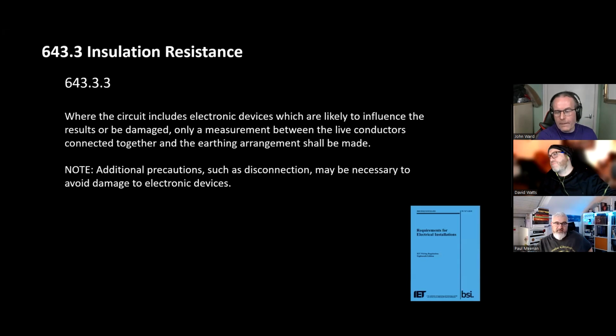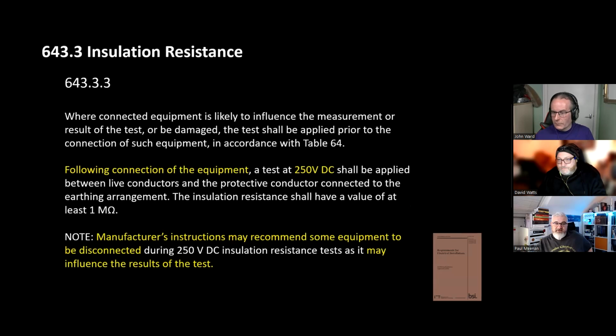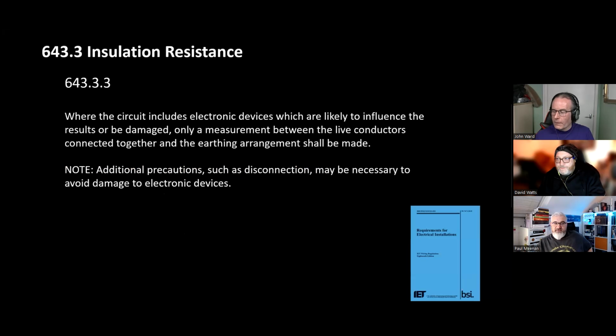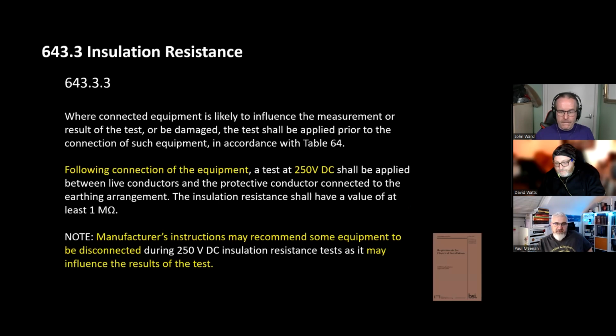So let's just move on a bit here. Where the circuit includes electronic devices which are likely to influence results, and this is the excuse now for not doing it properly. Only a measurement between live and conductors connected to an earth shall be made. It then says additional precautions such as disconnection may be necessary to avoid damage to electronic devices. Yeah, that's fair enough. So this to me is second fixing, going back and doing it. Fair enough. Verifying after you've put all the floorboards back and all the rest of it.